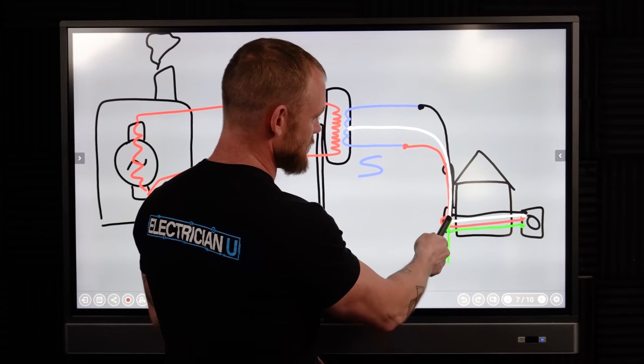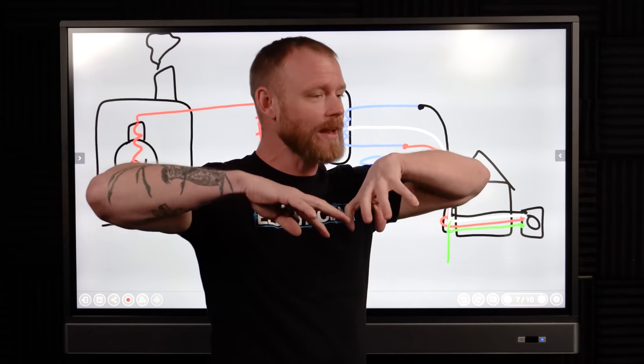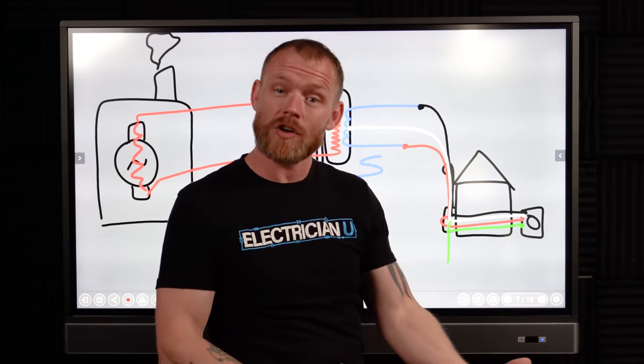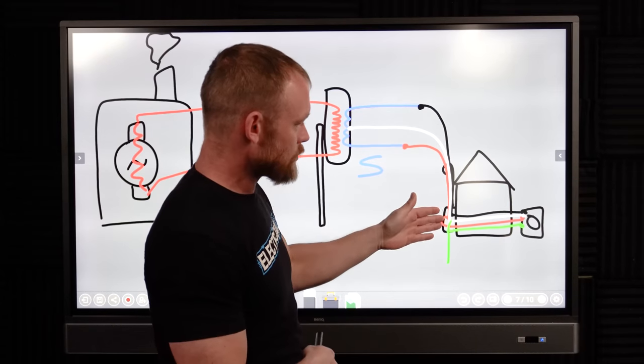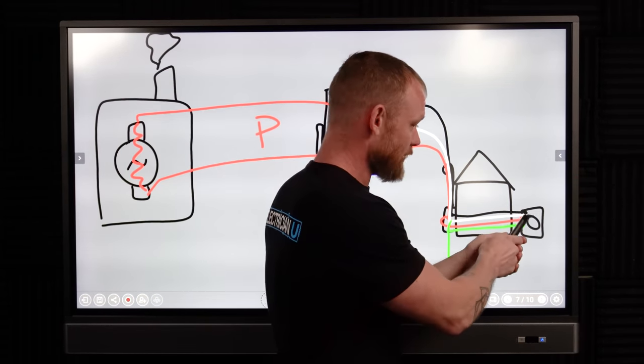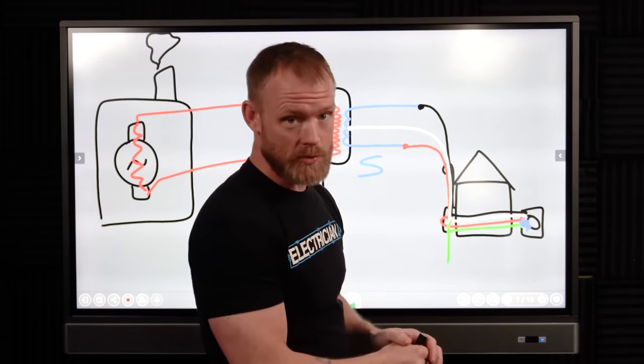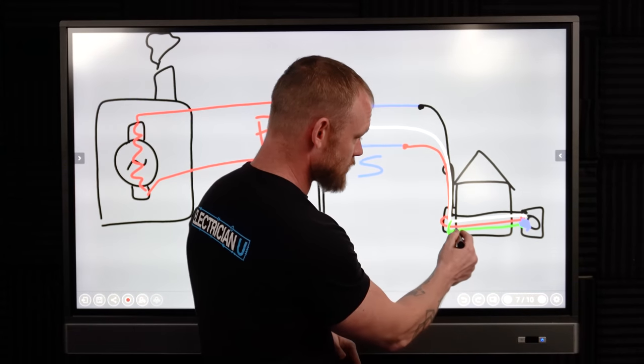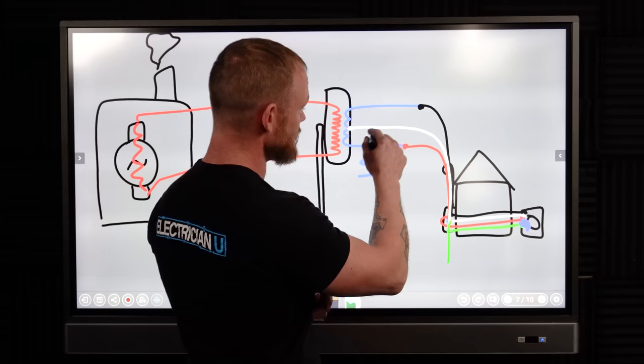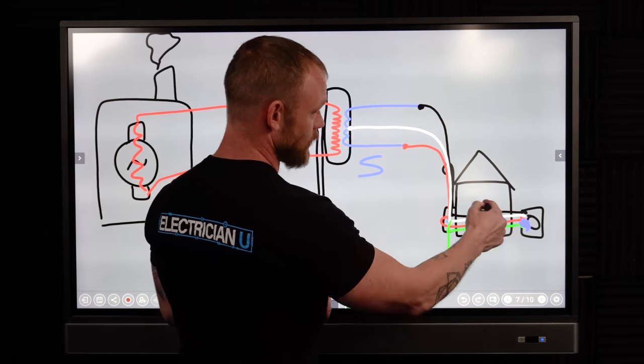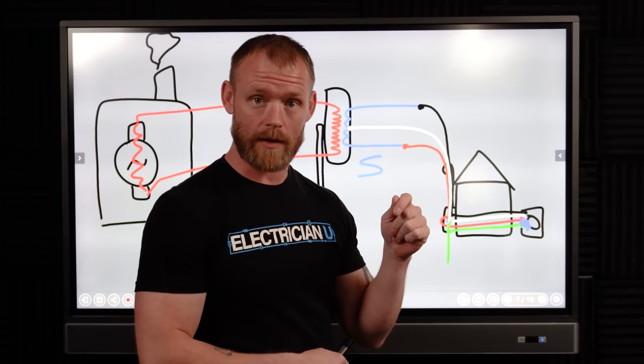The ground is not connected to the rest of the system directly — we run a ground that bonds every piece of metal around electrical equipment that somebody could potentially touch. We bond our neutrals and grounds together so that if a hot conductor makes contact with the metal of, say, a washing machine, the fault current can travel down the grounding conductor — still connected to the neutral — completing a circuit back to the transformer. This sends a huge amount of current through the circuit and trips the breaker.